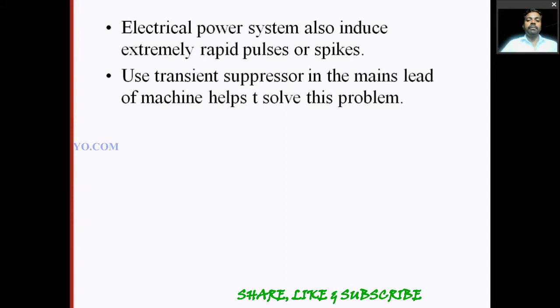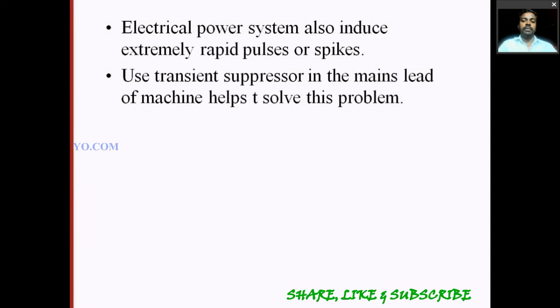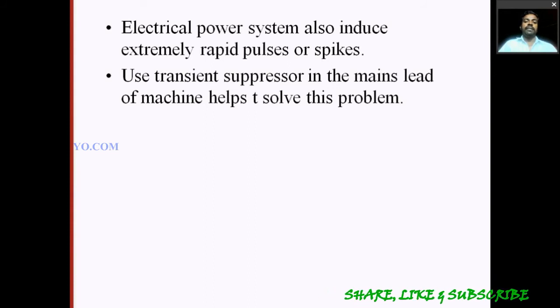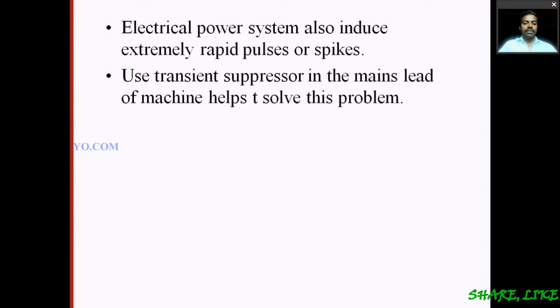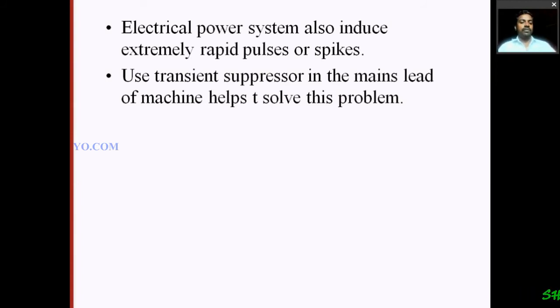The next source is the electrical power system. The electrical power system — including generators and inverters — externally creates rapid pulses and spikes that completely affect the ECG signal. A transient suppressor in the mains lead of the machine helps to solve this problem. Using a transient suppressor instrument helps reduce these rapid pulses and spikes.